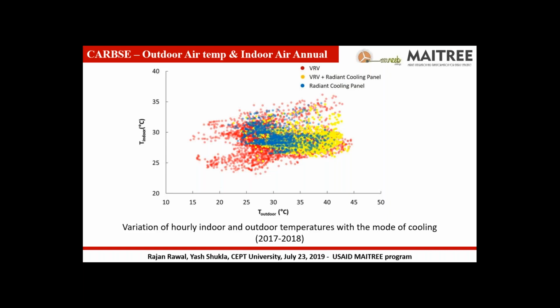And sometimes when there is a peak load, or if you have a high moisture load, you have to operate both the VRV and radiant cooling systems. This graph shows the scatter plot for different indoor and outdoor conditions. When you are operating the radiant cooling system, you see a much flatter curve compared to the VRV systems, where you see a slight slope with outdoor temperature. So the indoor temperature remains very uniform with radiant cooling, and does not change as much as it does for the VRV systems.